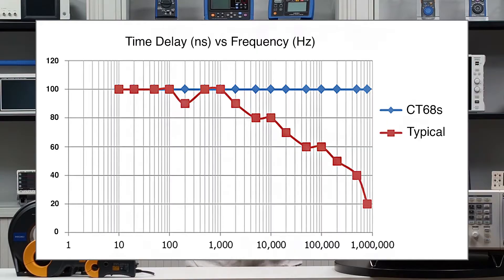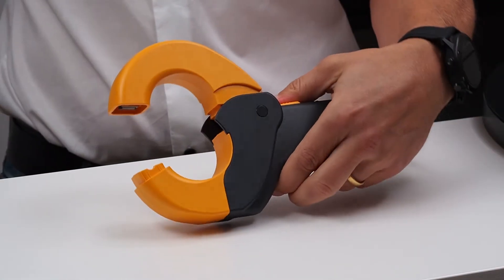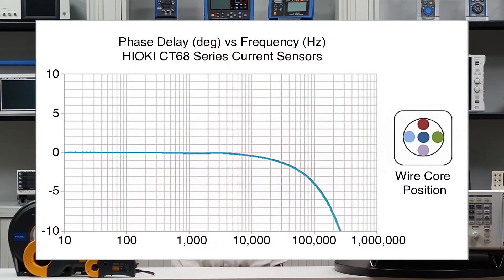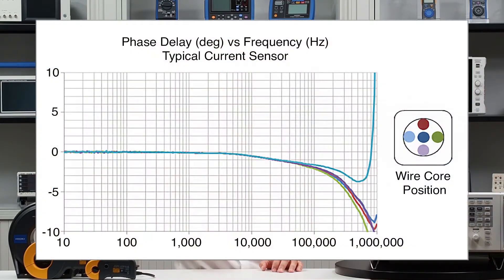Here is what would happen with a typical current sensor. A sensor where the time delay values are different depending on the frequency makes phase shift compensation in a power analyzer much more difficult — because which value do you use as your deskew parameter? Another thing that makes Hioki current sensors special is that the phase delay is not affected by where your wire core is located within the sensor during measurement. The reason you can only see one single line in the chart is that the phase delay curves for all five measurement positions are the same. Again, this is not a standard feature — typically the position of the wire core within the sensor produces results that look more like this.